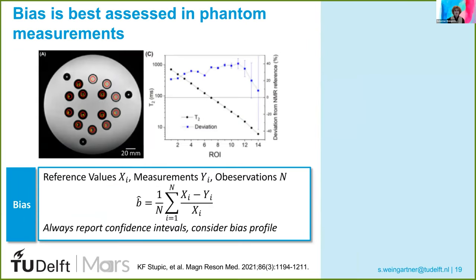Having known our reference method, we can finally define our bias. Taking a phantom object with n observations — in this case, different phantom points — if we take a reference measurement as well as a measurement with our method in each point, the overall bias can be defined as the average relative deviation of these two. As always in metrology, remember to report the confidence intervals for this. Also, bias may be dependent on the true value, and therefore it may be considered to plot a bias profile, which depicts the bias as a function of the true value, as shown in the plot to the top right.